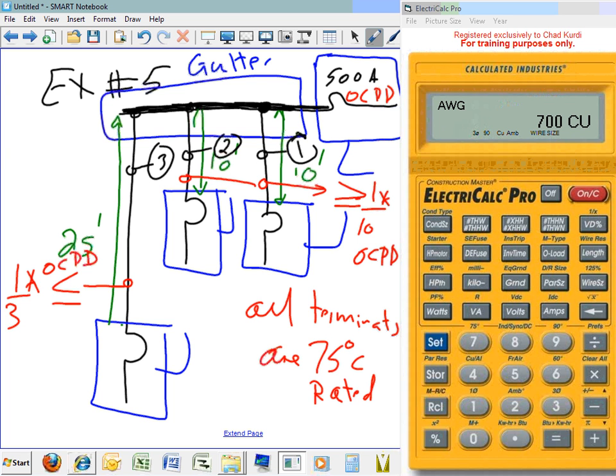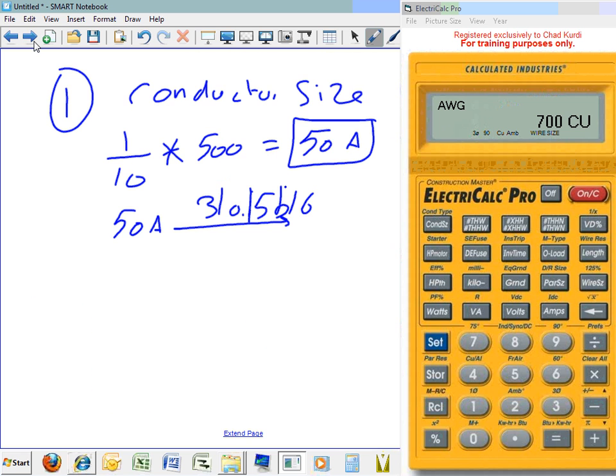Did you see the disclaimer here? That's why I'm going to size this one based on what? The 75 degree column. Can you give me a conductor from the 75 degree column? Number 8. Otherwise, it has to be number 6. So that will be 4 conductors, number 8.